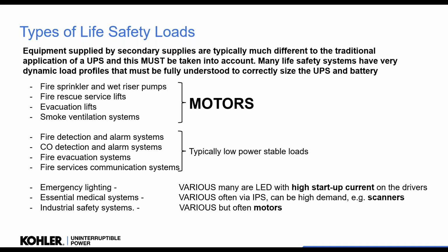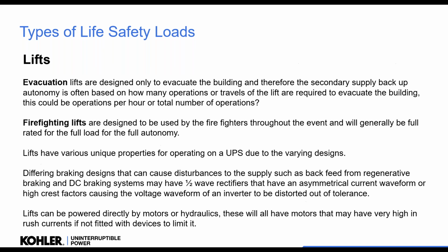Then we have emergency lighting, obviously very variable, different LEDs, different drivers. The medical systems in there, again, different IPS transformers. But then you have other things like scanners, which have a very strange demand, often pulsing current regularly. So it is very difficult to size for the UPS maximum size, and also for autonomy, because the loads vary all the time. So we have to look at them and be very sure we're getting it right.